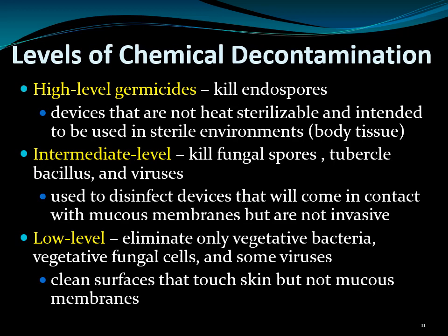Now, what are the different levels of chemical decontamination? I have already told you there are three levels: high level, intermediate, and low level disinfectant. High level is nearly a sterilant and kills the spores. So for critical devices which come directly in contact with sterile cavities, like in the OTs, high level disinfectants are needed. Intermediate level kills fungal spores, tubercle bacillus and viruses, so they are useful for semi-critical devices.